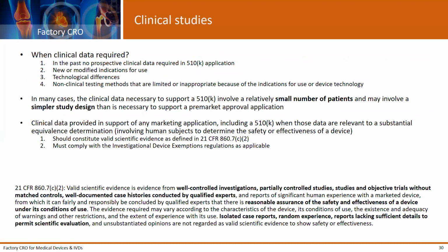Clinical studies. When are clinical data required? In the past, there was no prospective clinical data required in 510(k) applications. But clinical data is required when we see new or modified indications for use, when we see technological differences, and when we see non-clinical testing that was inappropriate because of the indications for use or device technology.